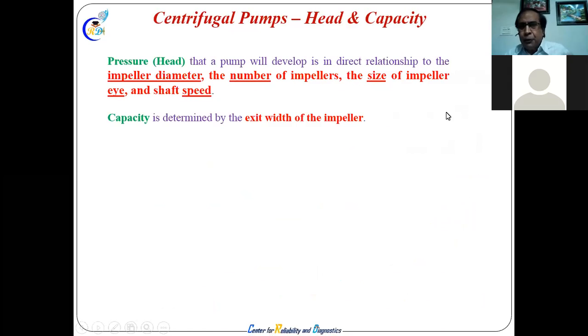Okay, so head and capacity, pressure head. If you want a change in pressure head, you change the diameter, number of impellers, size, or shaft speed. So you can change it, and that's what it is. It is good if we do not have to change. We select a pump in such a way that we don't want to change afterwards. That's good engineering. When we are not able to do good engineering or foresee our future requirement, it is very bad for a plant. Today they're installing a machine, and within 2 years, 3 years, they want to go for a VFD. It is not good engineering, I say, because either you have not visualized what the requirement is after 2 years, 3 years.